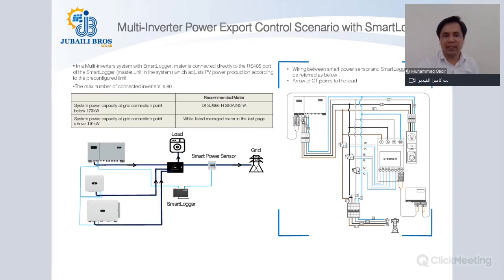Multiple inverter power export control scenario with a smart logger. If you have multiple inverters, which could be of any quantity, you can always use a smart logger as well, which is a universal logger for all the different inverter models that Huawei has. The connection from the smart power sensor in this scenario will go to the smart logger, and then from the smart logger the connection will be made to the inverter. The smart logger will also do the monitoring and send the command for changing the MPPT points in case a control is required to reduce the output of the PV plant.